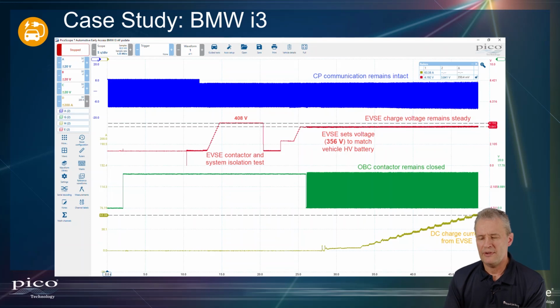Here we are again with the EVSE contactor and system isolation test. Remember, at this point the contactors are still open, it's just testing the line there for insulation fault. The EVSE switches on. It starts to progressively increase the voltage. When the voltage matches that of the battery, and in this case, at this one we are 356 volts to match the vehicle high voltage battery.